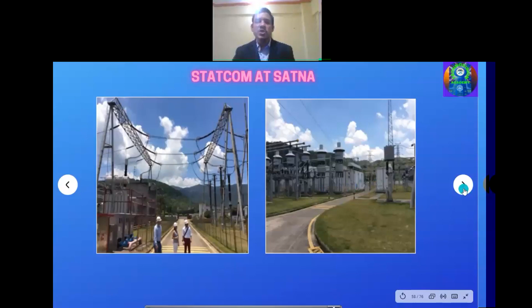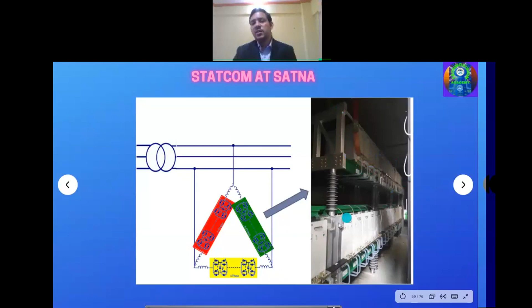We know they have used IGBT modules. When we connect IGBTs in series as well as shunt combinations, it forms the modules. And when I arrange these modules in either star or delta, it forms the modular form. So here in Satna, the IGBT valves are connected in a delta fashion, R, Y, and B, like this. This is a transformer connected with the grid, and at the low voltage side we have connected these IGBT modules, and this is the cubicle where series and shunt connected structures are shown.